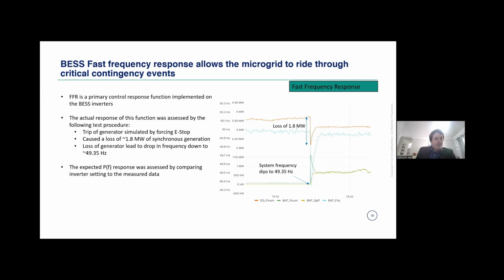Obviously, this is a fairly tricky application to test or assess. So what we ended up applying is to create a dip in frequency within the system by tripping one of the generators, forcing the e-stop, which led to a loss of 1.8 megawatt on the system. This entailed a drop in frequency down to 49.35 hertz, which required the battery system to respond.